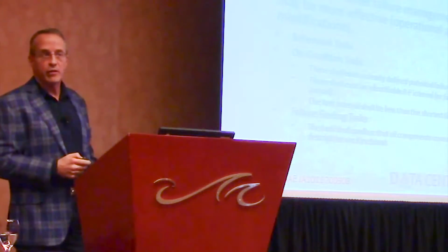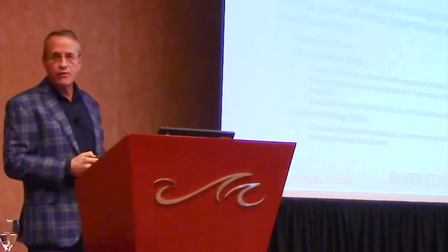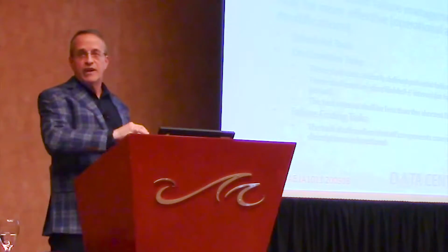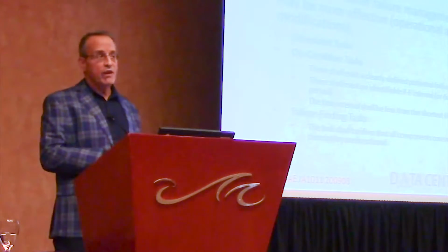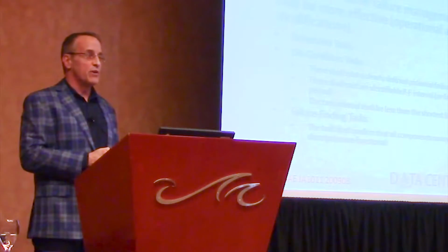These failure finding tasks we'll get to a little later, but this is where you induce a little risk into your environment. Failure finding is meant to uncover a failure you cannot duplicate in any way with the full function of a system. If the utility drops power to your facility, A through X is going to happen, and hopefully it happens with the right timing and in the right order. There aren't many ways to fake that test -- a tabletop exercise won't do you any good. You just have to do the big nasty: warn your customers it's coming, don't do it during a thunderstorm, and see how it goes. There's no way out.